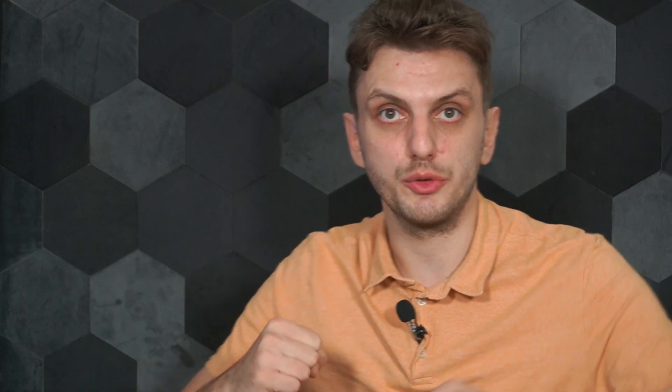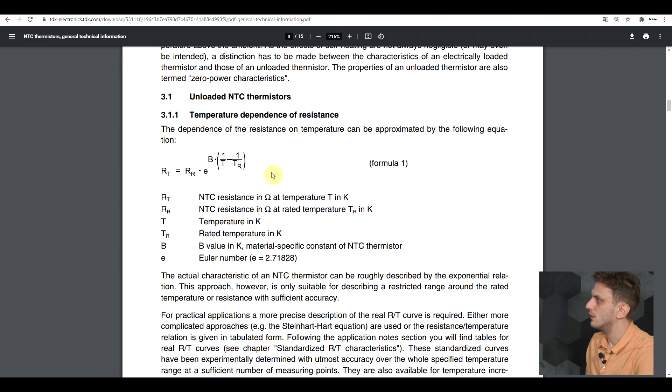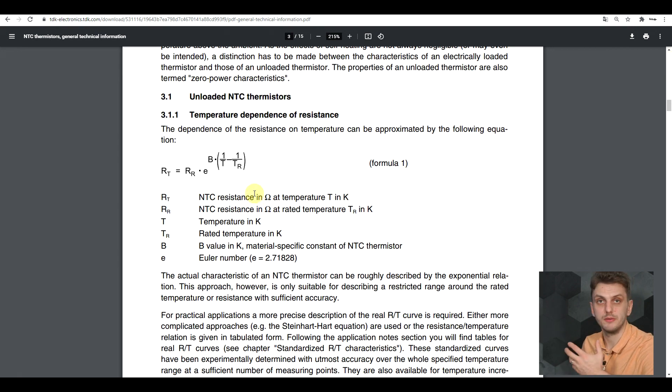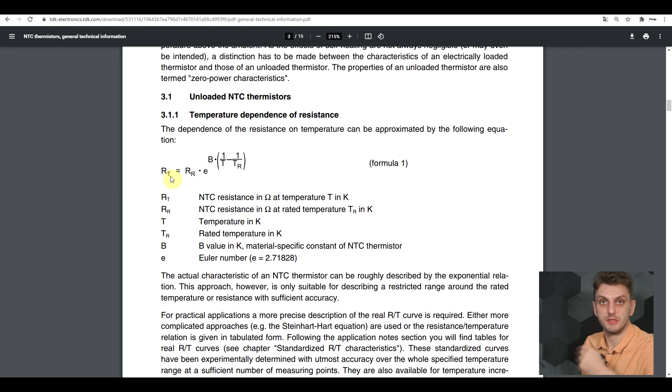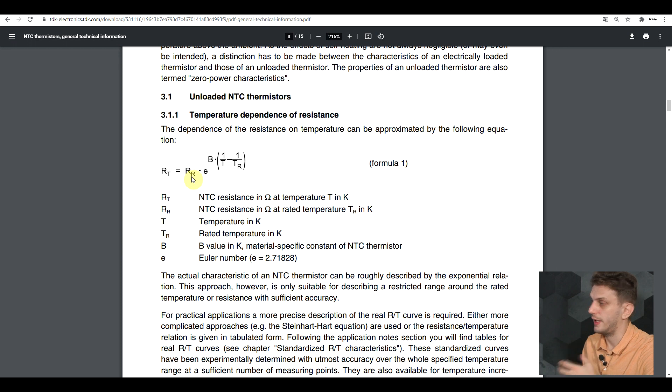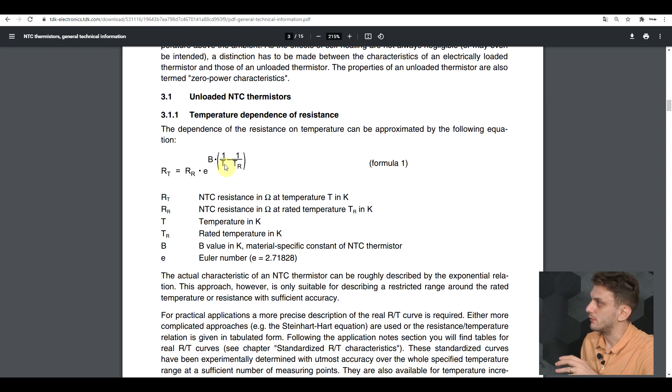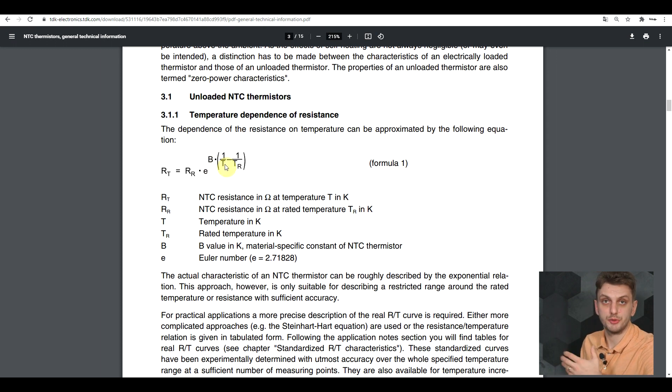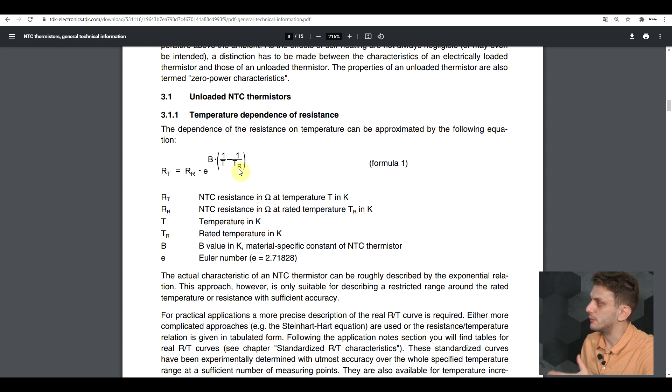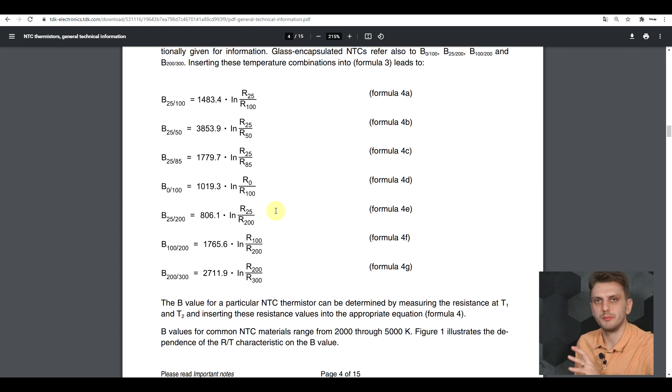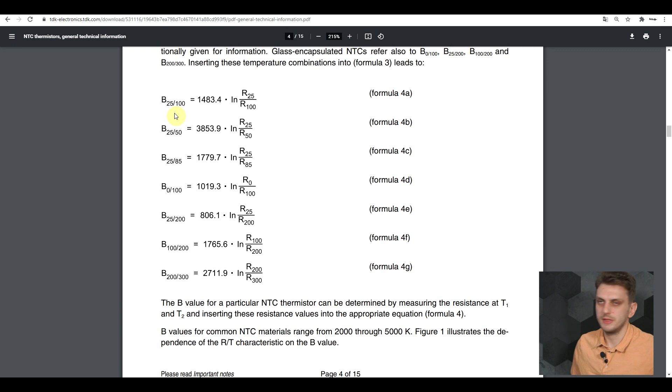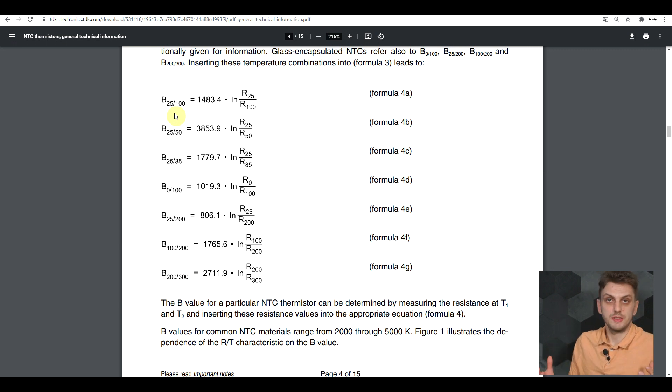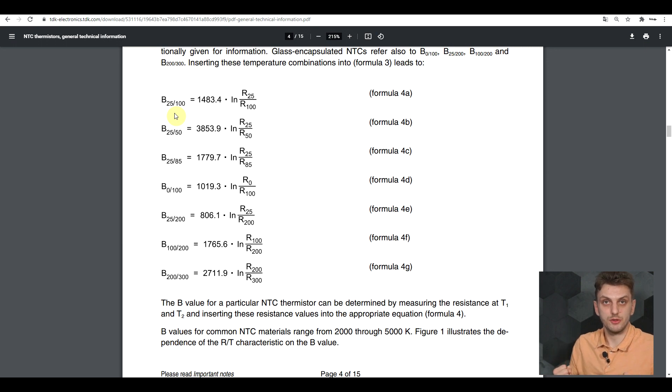First approach being the B-value approach. If we have a look in this application from TDK, we find here the formula for the B-value approximation. We will get the value for our thermistor at a specific temperature, based on the rated value at a rated temperature, everything multiplied by e to the power of the B-value multiplied by 1 divided by the temperature of interest, minus 1 divided by the temperature of the rated value. It's important to mention that this sort of B-values will commonly be found with some sort of subscript. This indicates the temperature interval in which they are valid. And outside of these temperatures, this formula will not give accurate results.